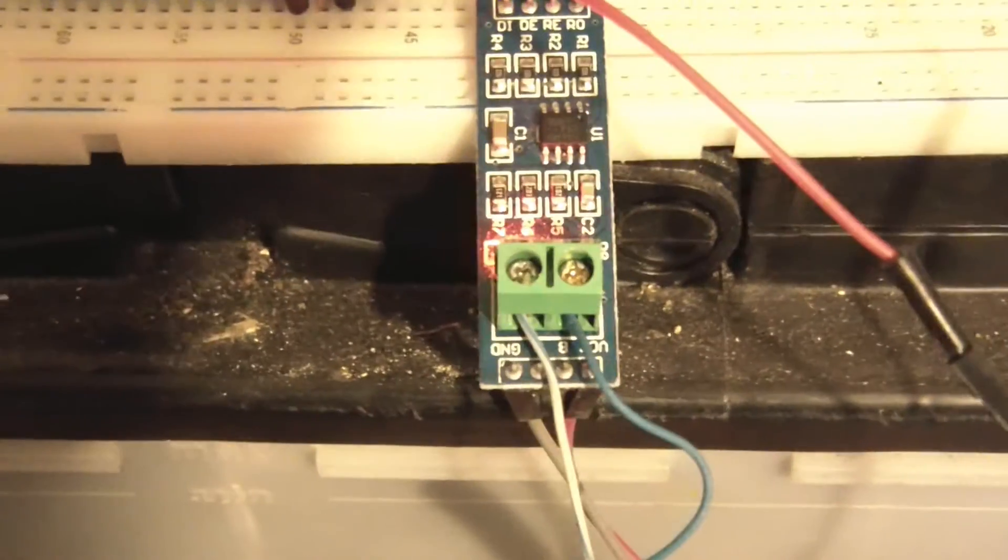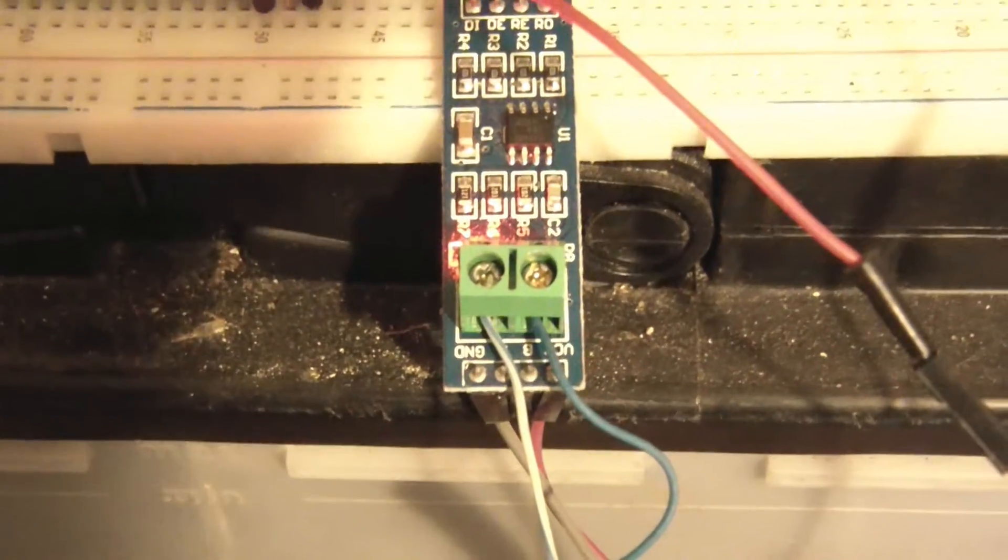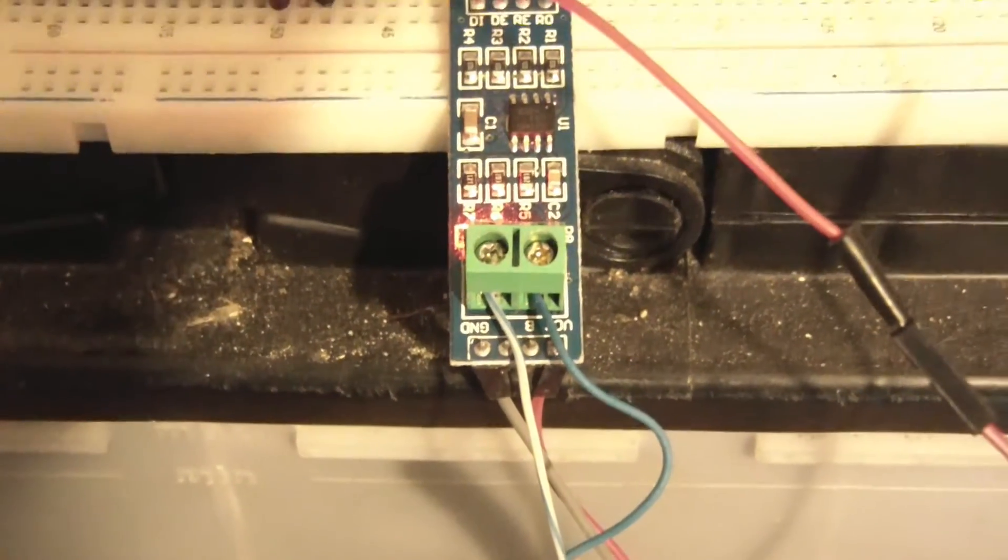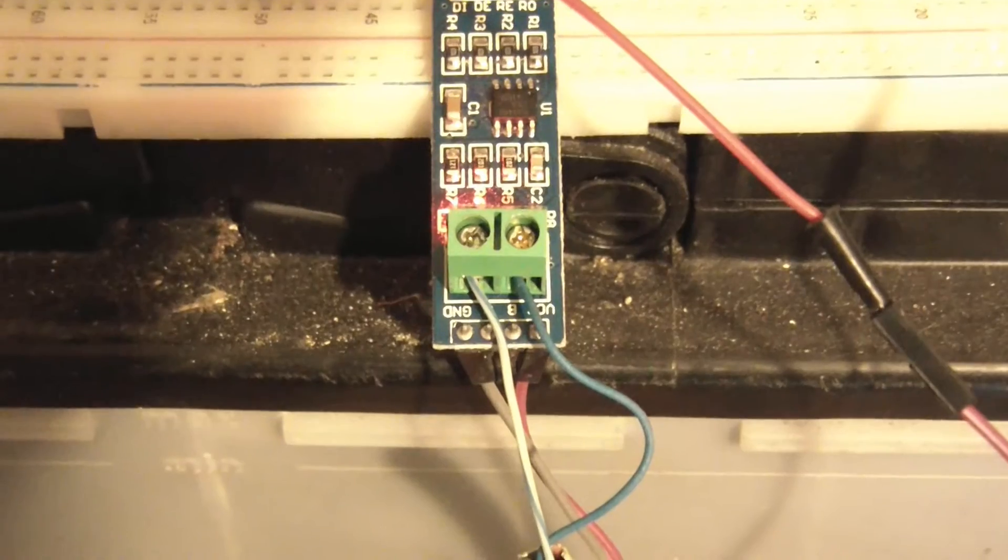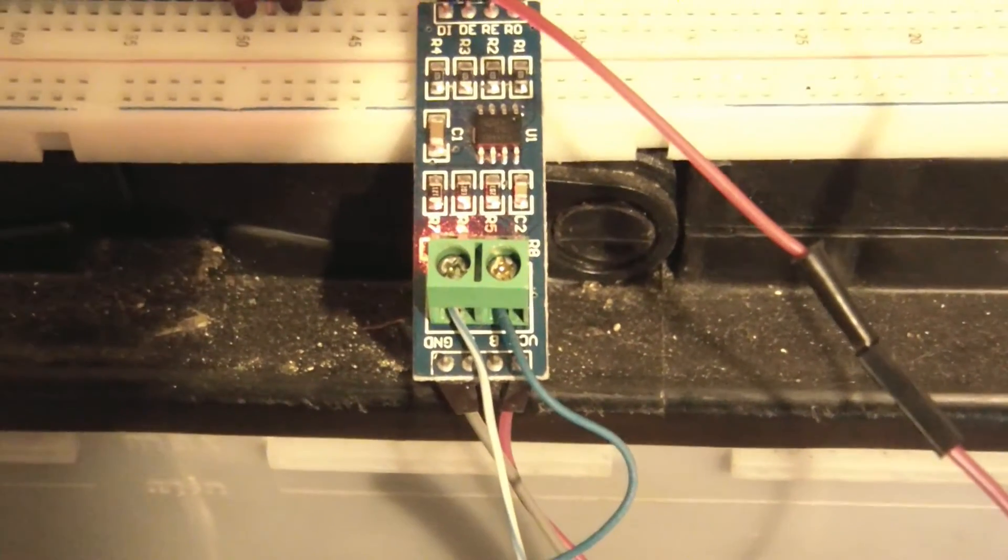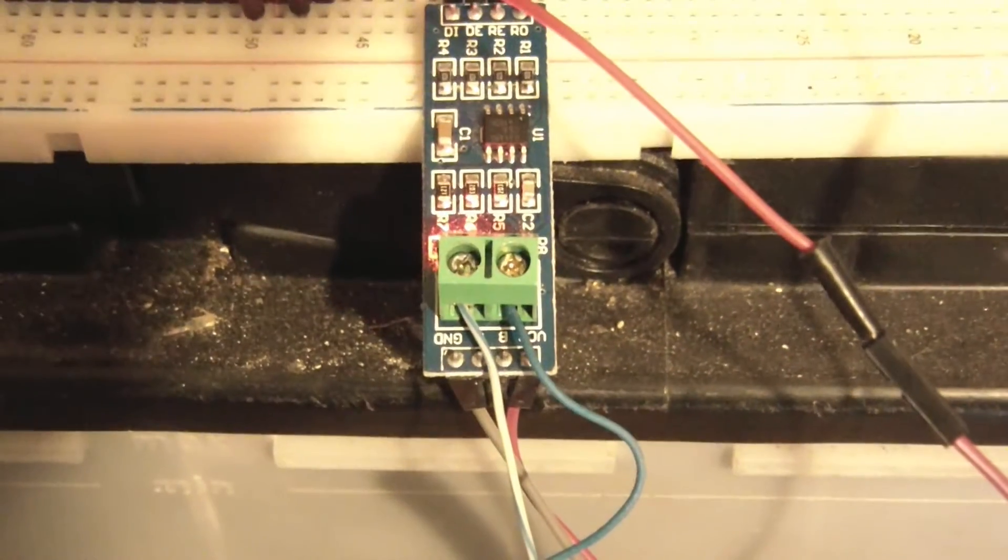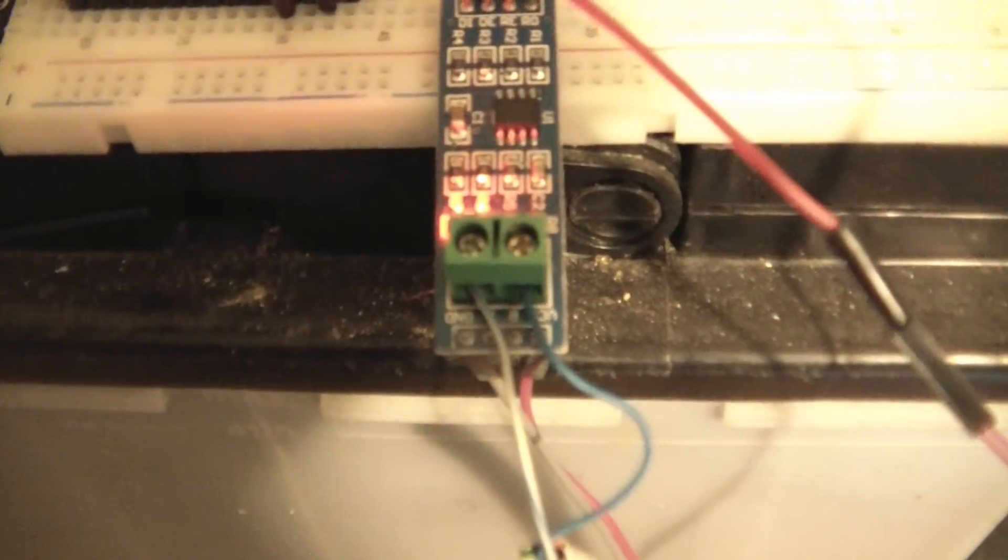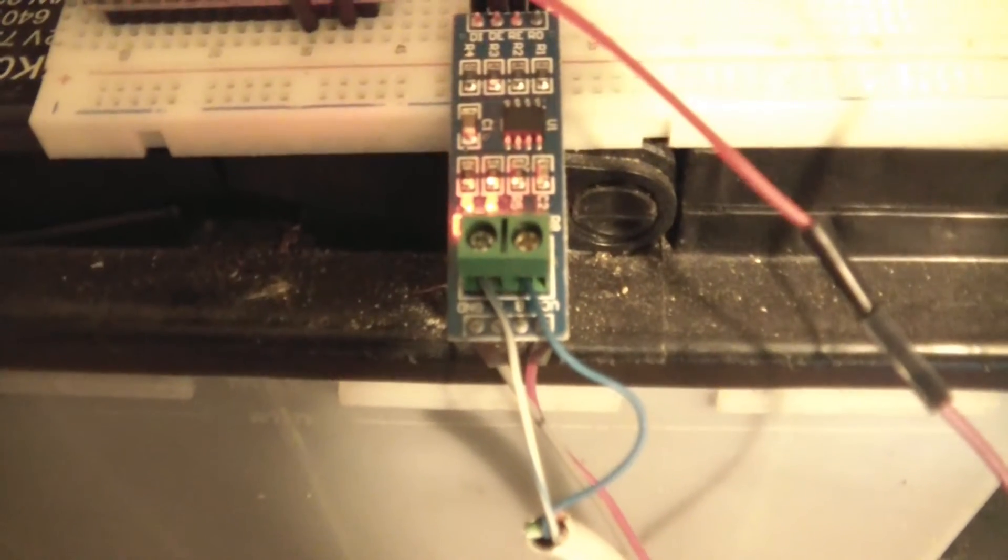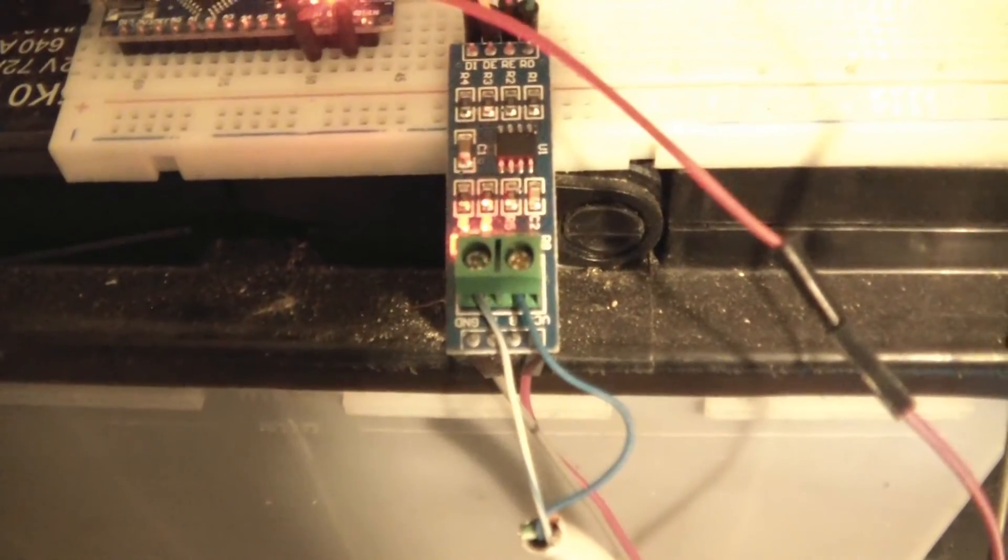So according to your documentation for your device, you will be able to find out which two of those pins are the ones that you need to use. And usually they'll be labelled in the documentation as A and B. You can see in the middle there, there's B and A. So in the specification document of the device, you should be able to see that in there somewhere as well. There are ways of finding out by doing tests, but I won't go into that. So we found the A and B pin of the eight pins, and then I've cut the rest back.